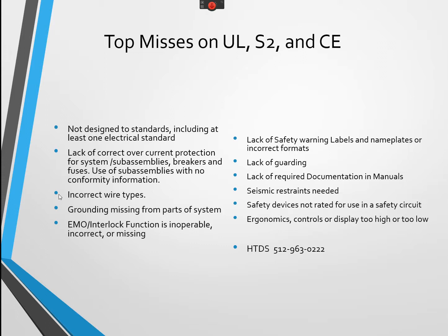The next one is incorrect wire types or sizes. In the US, typically any power circuits, anything running at line voltage, needs to be 14 gauge wire. You can use smaller gauges when you go to the CE standards. However, the reason that 14 gauge is required in North America is that it's robust enough that it doesn't get damaged while you're building a custom piece of equipment. That's a simple thing to think about. You can use smaller gauge wire, but then go back to the correct overcurrent protection. Any wire smaller than 14 gauge is going to require an overcurrent protective device rated for that smaller wire size.